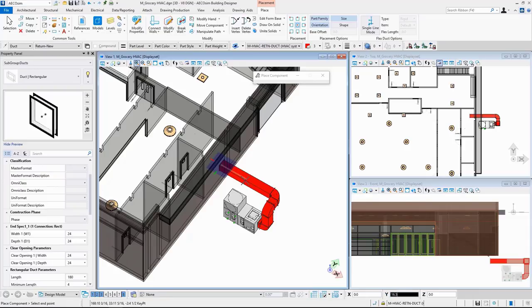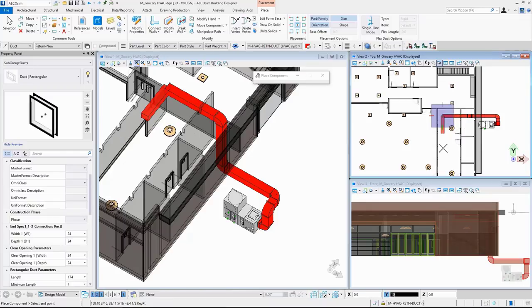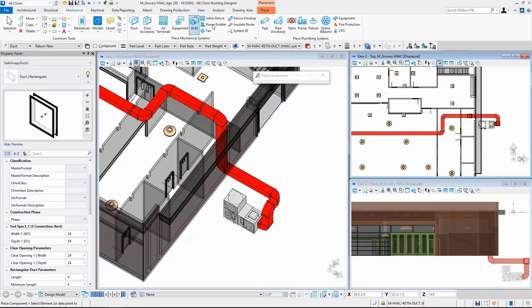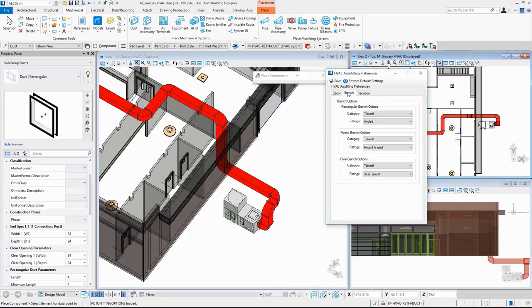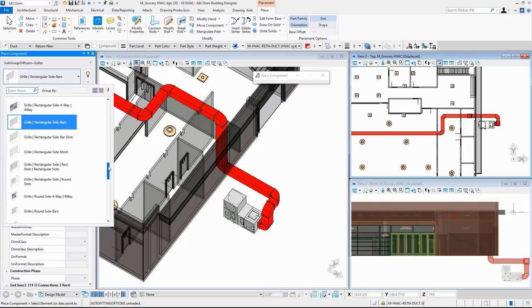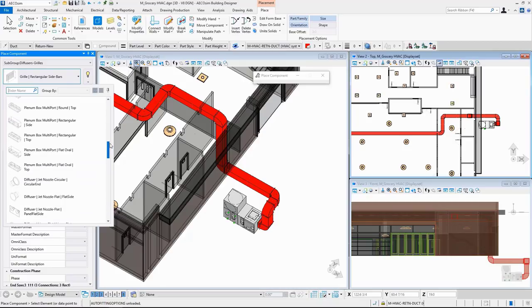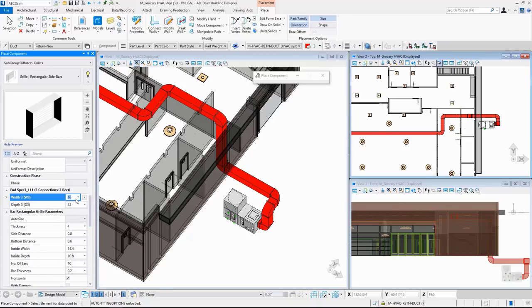You can also click on any data point to create a duct and use different views to draw ducts more intuitively. I have used View 2 to draw ducts from the top view without having to exit the tool. The bends and branchings while drawing ducts can be controlled by the auto-fitting preferences, which has settings for Elbow, Branch, and Transition. A grill from the delivered dataset is placed on the duct — there are many pre-designed 3D models of air terminals available. I select the grill, scroll down in the Place Component dialog, and resize it according to my requirement; the size of the grill changes in the preview window as well.